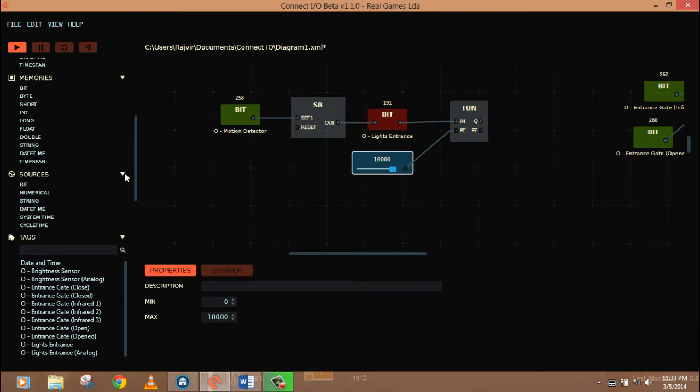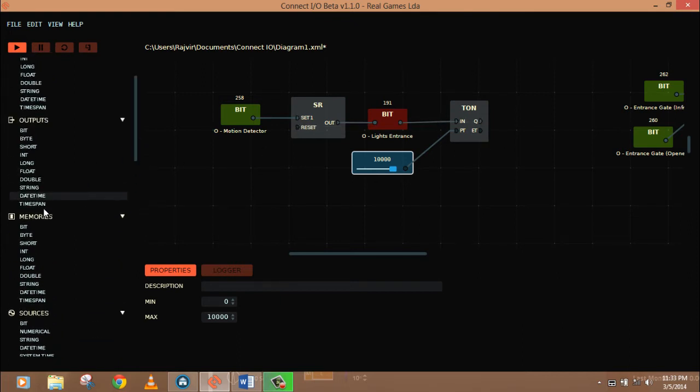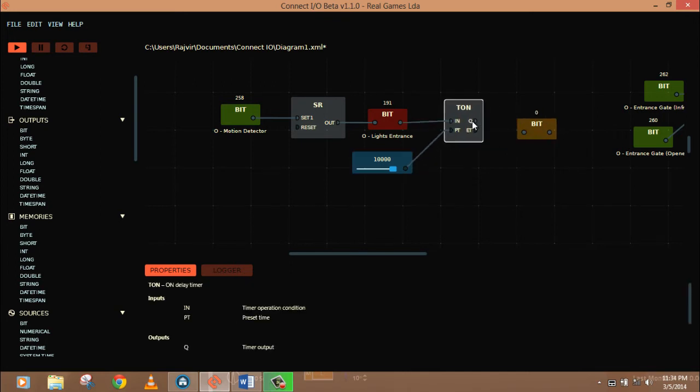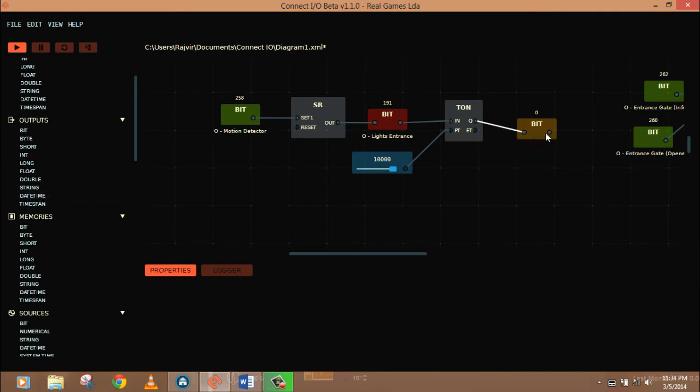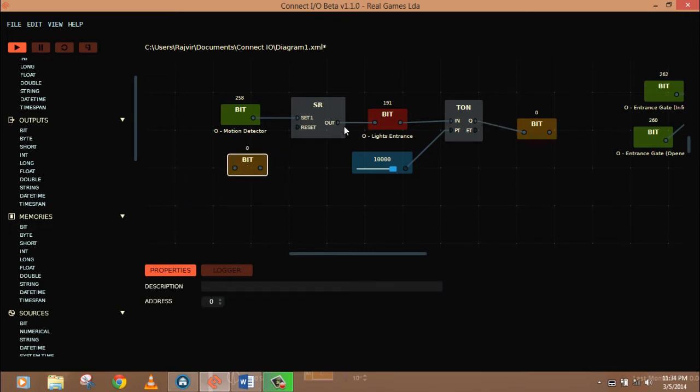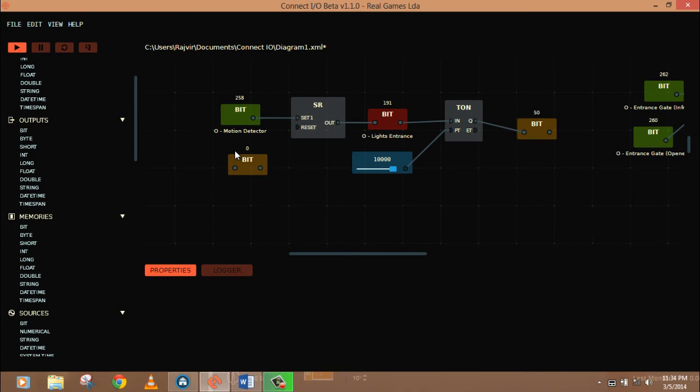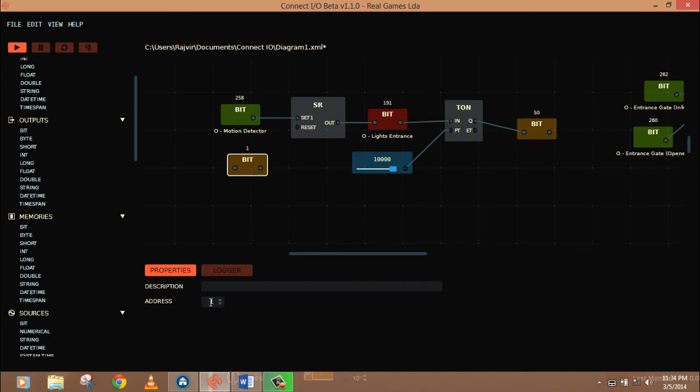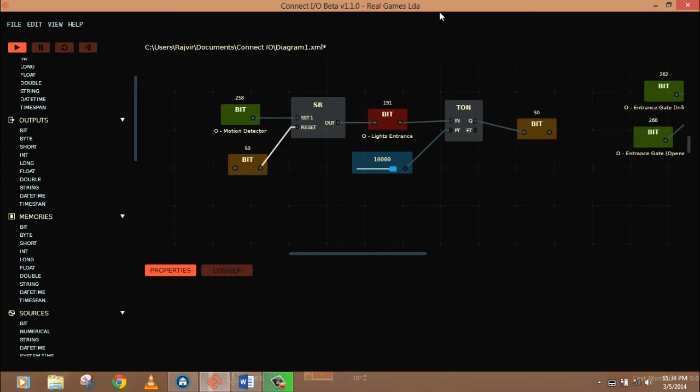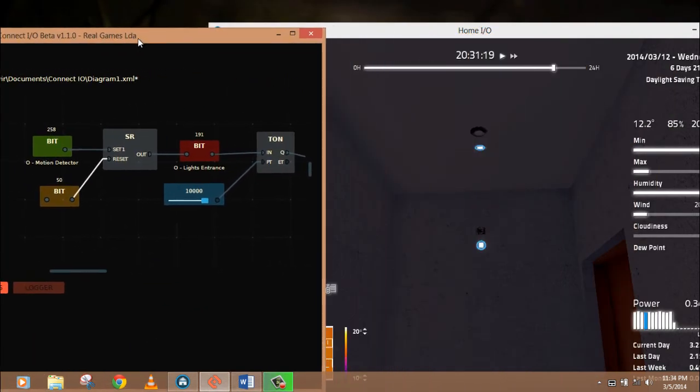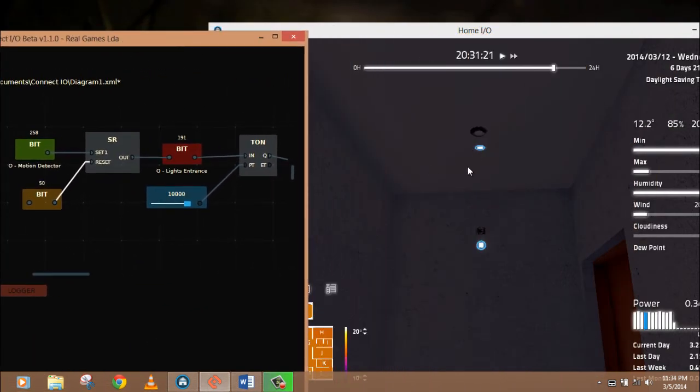So the alternative is we'll take a bit from the memories. Take a bit and you connect this bit with this output. Now we'll take another bit, because even this cannot be connected here. We will take another bit. This is just a way to connect your inputs with different blocks. So here we can assign an address, let's say address 50. We have to assign the same address to this bit, because then this will respond to this bit. If this is on, this will be on. So let's take here 50 as well. Now the function here is we have to get to reset.